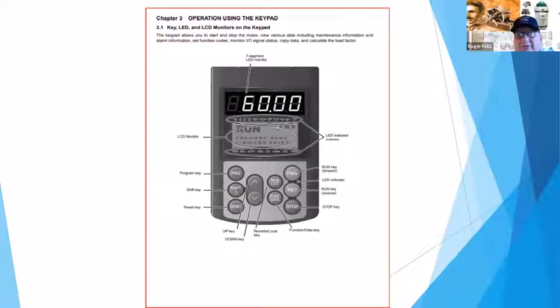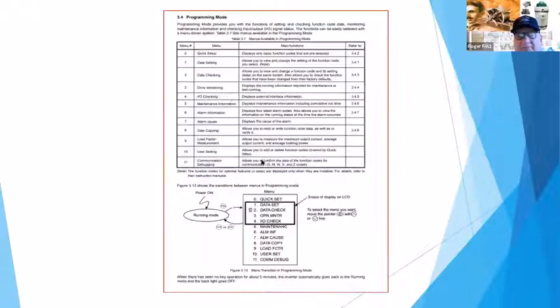And then they have a lot of fault codes inside the drive. Well, it's good to read up on that and understand what those fault codes really mean. Under voltage, over voltage. But again, those may be the setting in the drive of what the upper and lower limits are, because these are shipped all around the world and they have multiple parameters adjustable for different countries. So that's all based on what their power source is. So the components may be able to handle 480 volts, but if it went to England, they may only be using it on a 400 volt circuit, 50 hertz. So it'll have a different set of parameters. So it's important to realize that you're controlling this, but again, keep it simple.